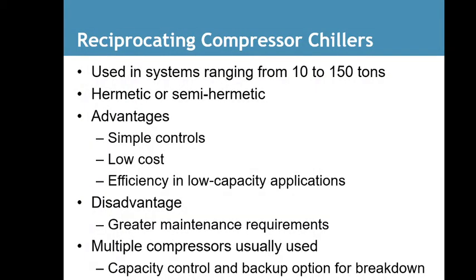Reciprocating compressors for chillers are used in systems ranging from 10 to 150 tons. Hermetic or semi-hermetic. Advantages are simple controls, low cost, efficiency, and suitability for low capacity applications. It's an important thing: reciprocating doesn't do high capacity. They do very low capacity. Disadvantages: greater maintenance required, multiple compressors, usually use capacity control, and backup operations for breakdowns.